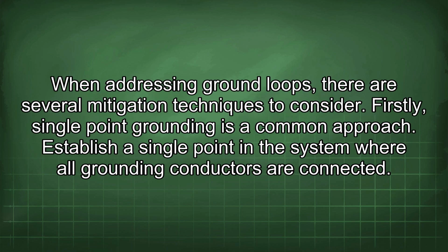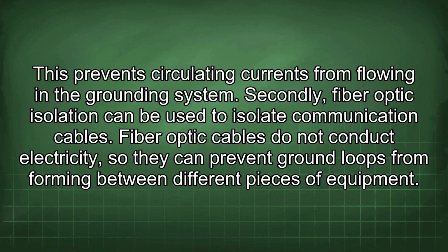When addressing ground loops, there are several mitigation techniques to consider. Firstly, single-point grounding is a common approach. Establish a single point in the system where all grounding conductors are connected. This prevents circulating currents from flowing in the grounding system.